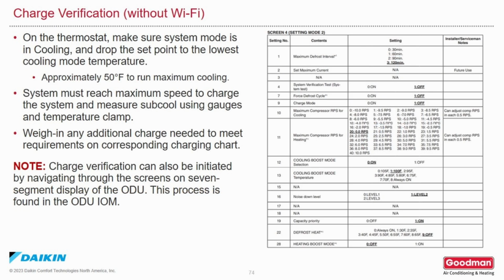Running charge verification without Wi-Fi. On the thermostat, make sure the system is in cooling mode and drop the set point to the lowest cooling temperature, which is approximately 50 degrees Fahrenheit, to run maximum cooling. The system must reach maximum speed to charge the system and measure subcool using gauges and a temperature clamp. Weigh in any additional charge needed to meet the requirements of the corresponding charging chart that can be found in the outdoor unit IOM.